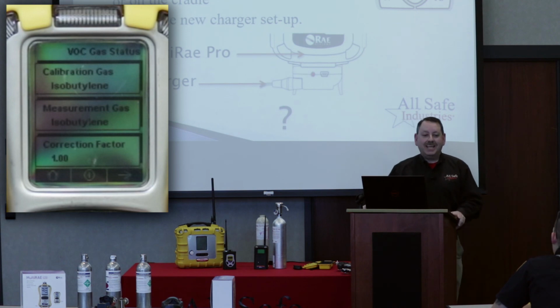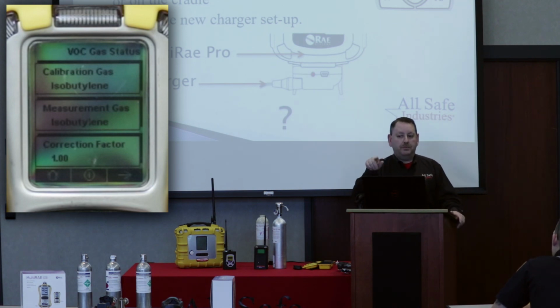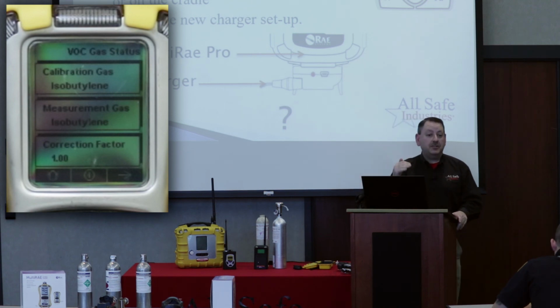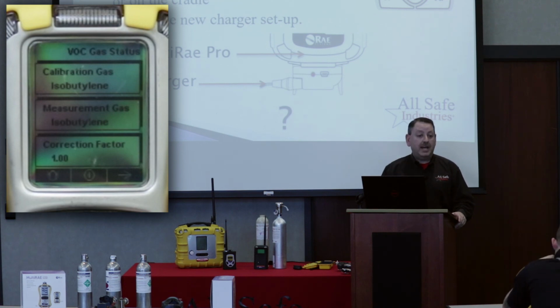Go ahead and hit your arrow button again. What's the next screen say? Okay, and then at the top of the screen, does it say LEL or VOC? VOC gas status. Very good. So VOC gas status, and some of you, depending on my demo meters that you're using, could see LEL gas status. It's reminding you what your current settings are. So VOC gas status, it's going to remind you that you're using the 10.6 electron volt lamp. It's going to point out that your calibration gas is isobutylene. And out of the box, it should say that your measurement gas is isobutylene.